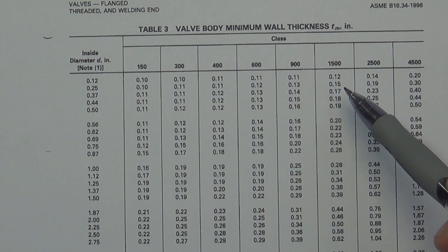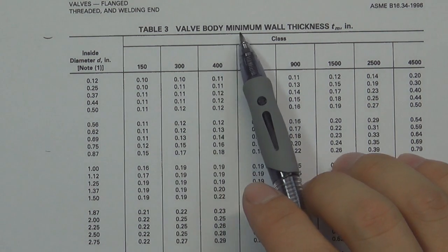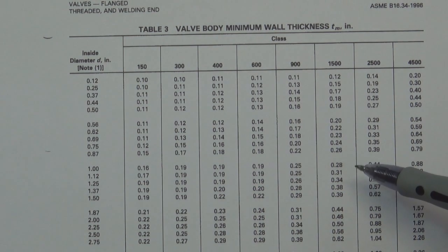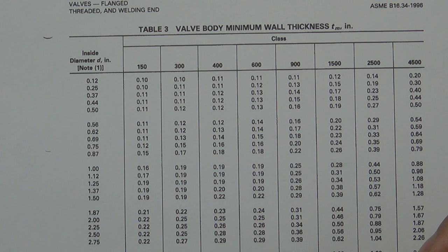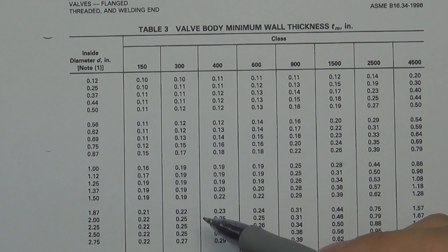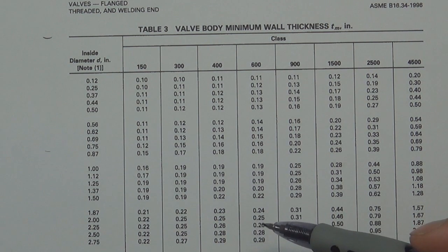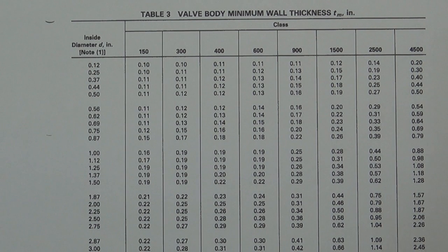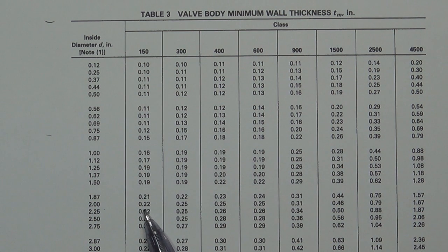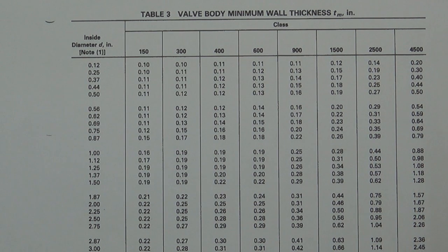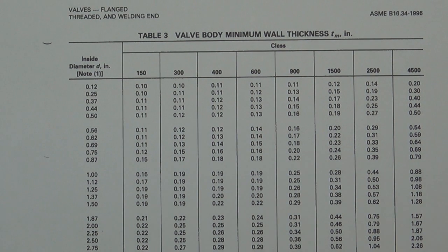This is the table from ASME B16.34, called the valve body minimum wall thickness table. In this table, you will find the minimum wall thickness for valves of different pressure classes and sizes. For example, if you are a valve design engineer and you want to design a 2-inch, class 150 valve, the wall thickness needs to be at least 0.22 inch thick. This is the minimum wall thickness for your valve, and from this table we can find all the thickness values needed to design a valve.